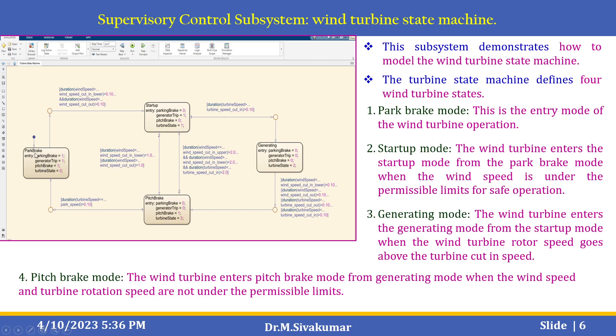The first one is the park brake mode — this is the entry mode of the wind turbine operation. The next one is the start-up mode: the wind turbine enters start-up mode from park brake mode when the wind speed is within permissible limits for safe operation. The third is the generating mode: the wind turbine enters generating mode from start-up mode when the rotor speed goes above the turbine cut-in speed. The fourth is the pitch brake mode: the turbine enters pitch brake mode from generating mode when the wind speed and turbine rotation speeds are not within permissible limits.